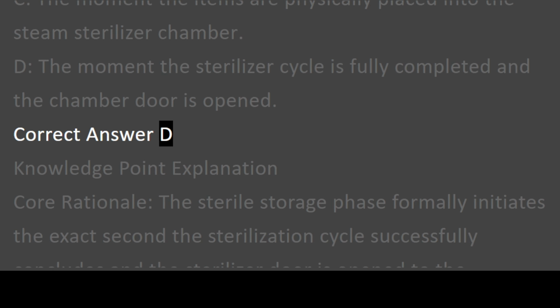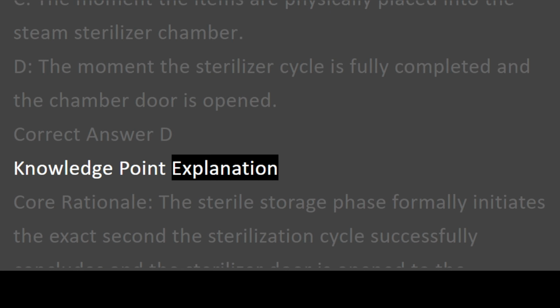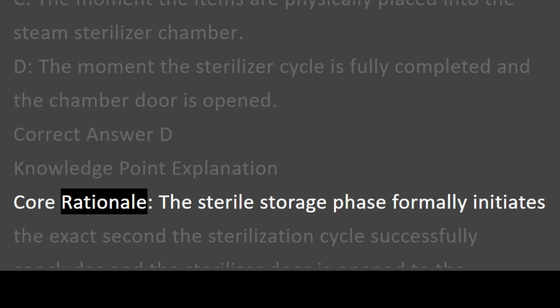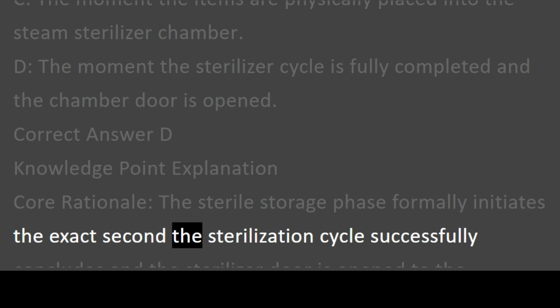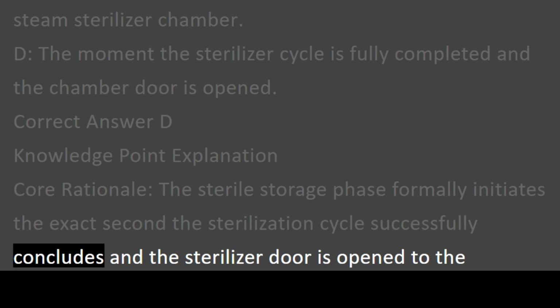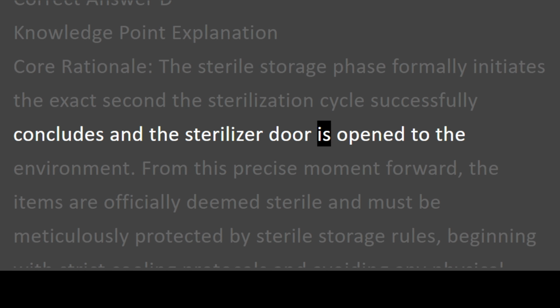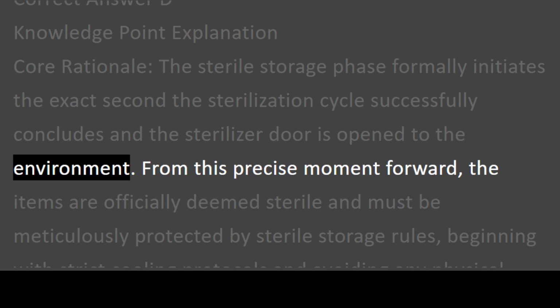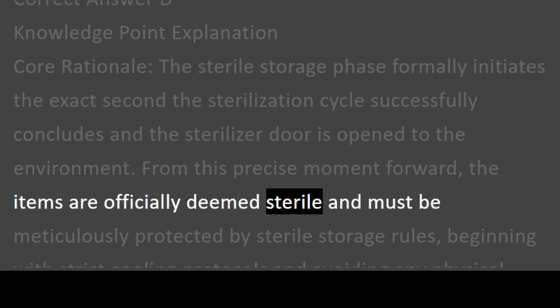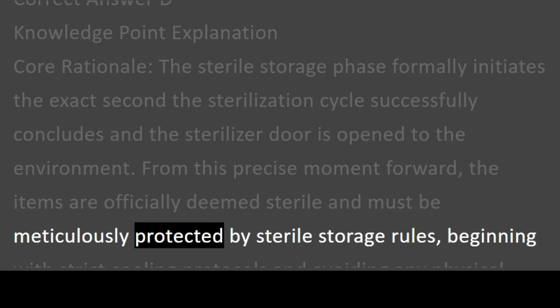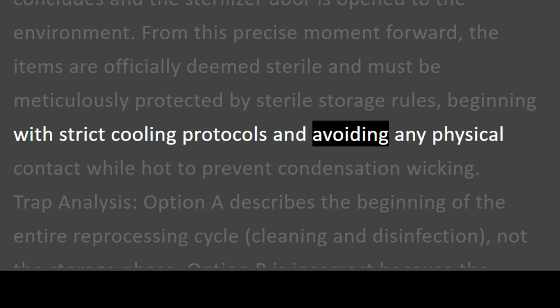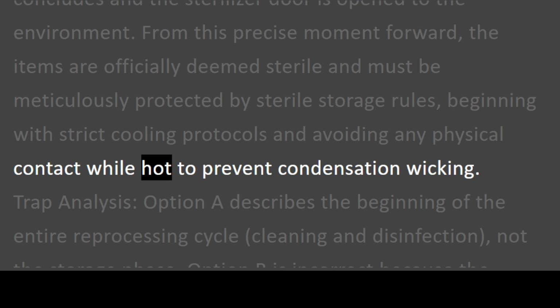Correct answer D. Knowledge point explanation. Core rationale. The sterile storage phase formally initiates the exact second the sterilization cycle successfully concludes and the sterilizer door is opened to the environment. From this precise moment forward, the items are officially deemed sterile and must be meticulously protected by sterile storage rules, beginning with strict cooling protocols and avoiding any physical contact while hot to prevent condensation wicking.